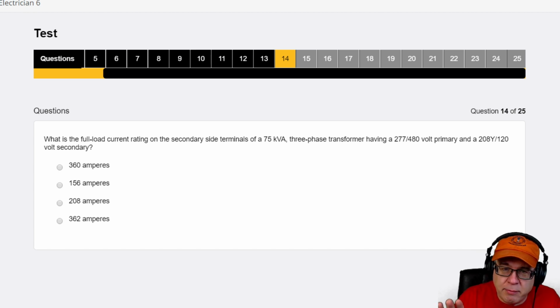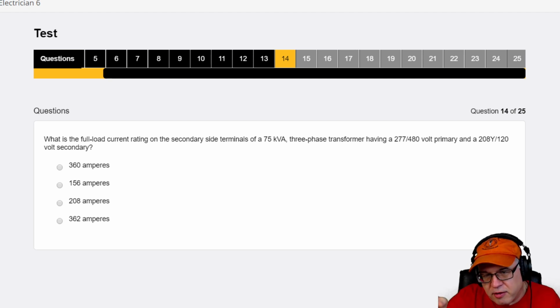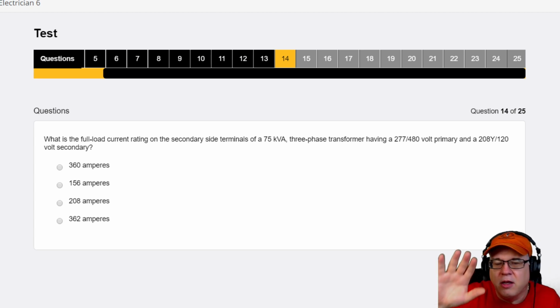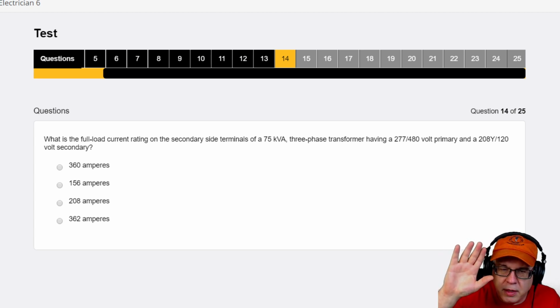Incidentally, if you're in an exam, just remember: if anything's 480 primary, use 831. If it's 208 secondary, use 360. That'll get you close enough to answer it. There is actually 360.256, but you can drop the 0.256 and just use 360, or 831 if it's 480.